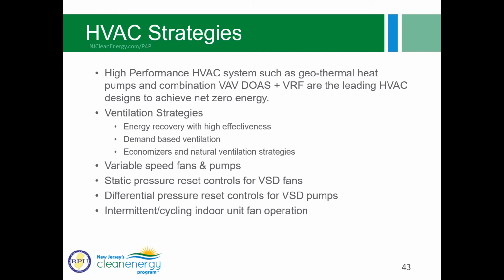So some ventilation strategies: energy recovery with high effectiveness, definitely demand-based ventilation, economizers, and then natural ventilation strategies. So we'll see in a few slides that some really high performing buildings have automated windows that will open up when outside conditions are good for providing natural cooling or natural ventilation.